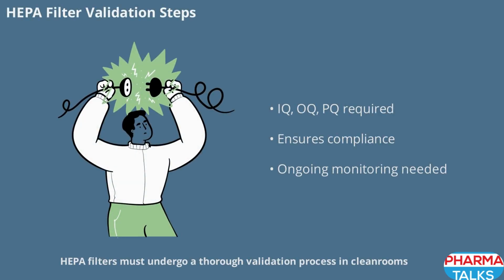HEPA filters must undergo a thorough validation process in cleanrooms. This includes installation qualification, IQ, operational qualification, OQ, and performance qualification, PQ. Each step ensures that the filter is installed correctly, operates as intended, and consistently maintains the required cleanliness level. Ongoing monitoring is also necessary to confirm continued compliance and performance over time.